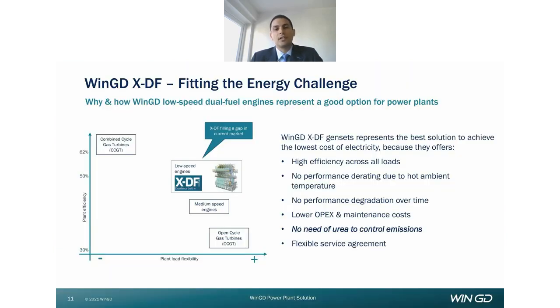As you can see from this chart on the left of the slide, our XDF are going to fill a gap in the current market for power generation. We position our technology in the middle between the very high efficient combined cycles, but less flexible solution, and the very flexible solutions such as open cycle gas turbines or medium speed genset, but less efficient compared to a combined cycle. So our opinion is that the XDF genset brings the right combination between efficiency and flexibility for power plants to produce energy with a low cost of electricity and at the same time a low emissions.